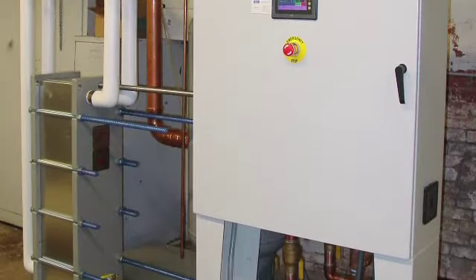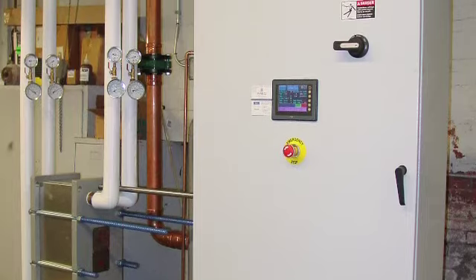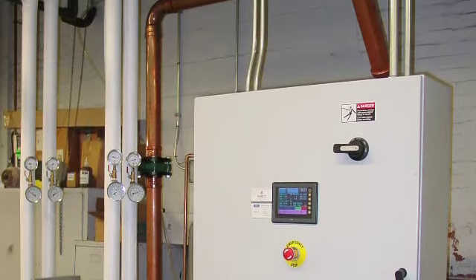The IMEC provided a turnkey installation for the customer, and it was really a seamless project. We designed a cooling tower and a heat exchanger skid and a piping network and controls that would take that hot water and preheat boiler feed water so that they would get the maximum energy absorption possible and lower their gas usage at their boilers. As a result, we are capturing the majority of the heat that would normally be wasted and rejected from the compressor.